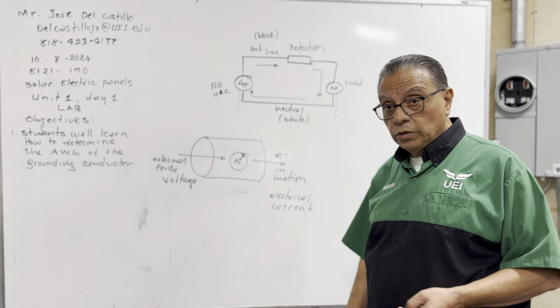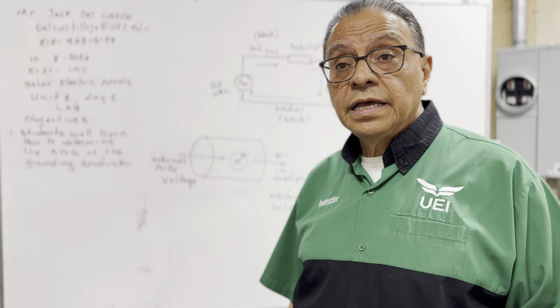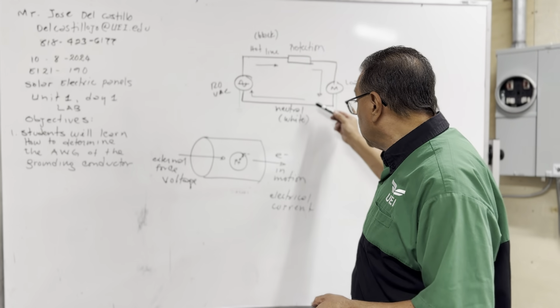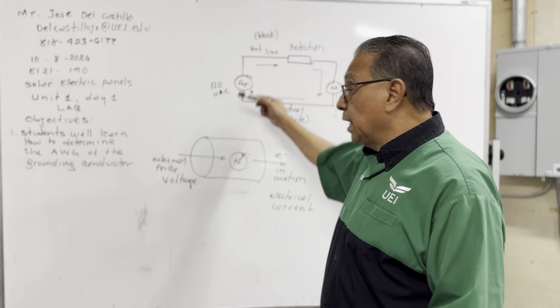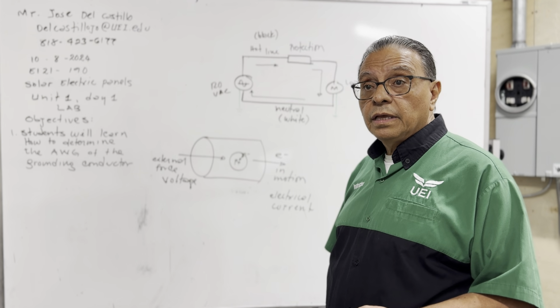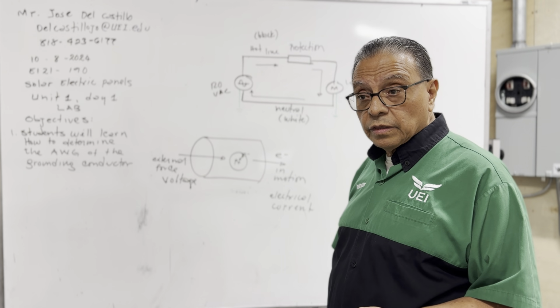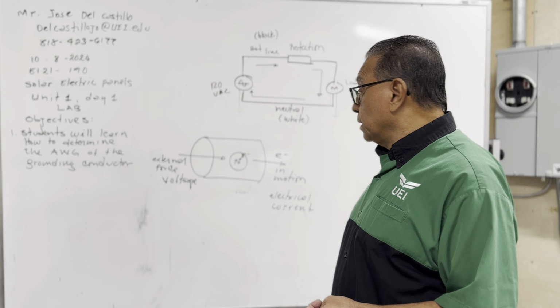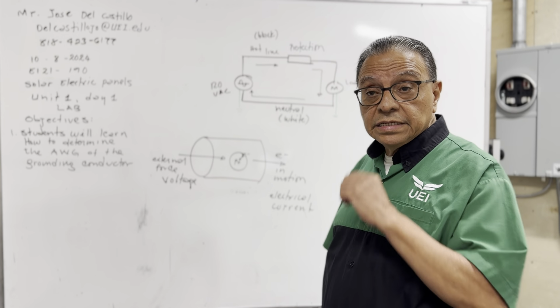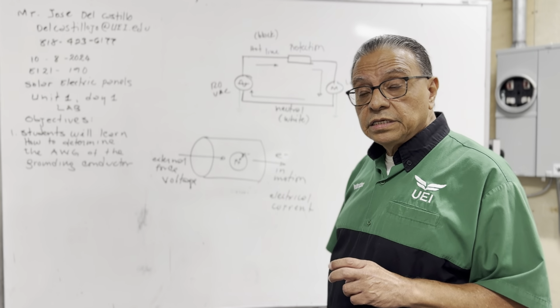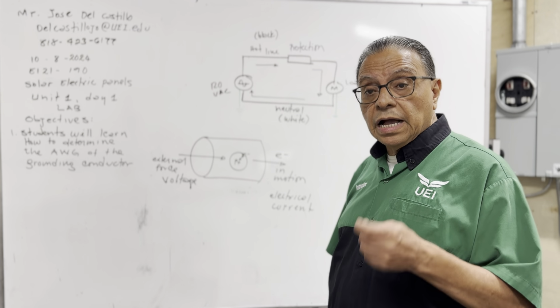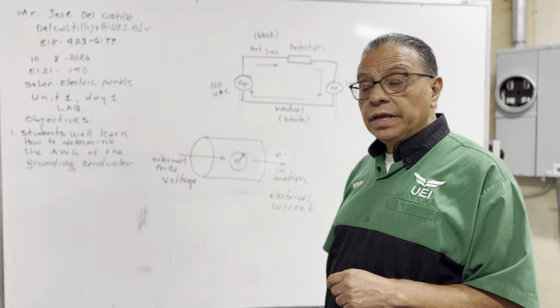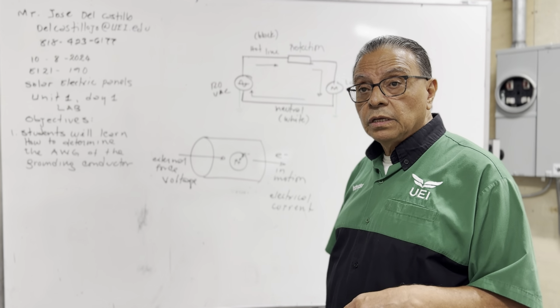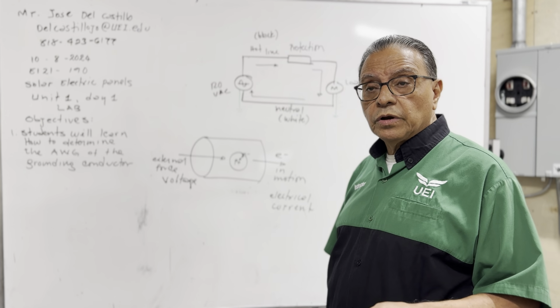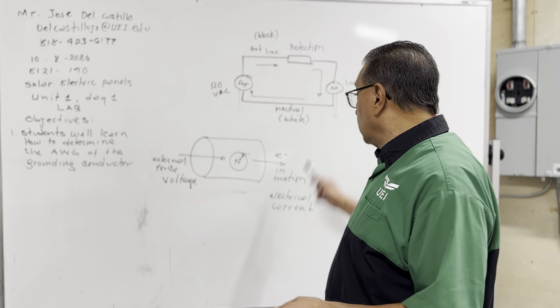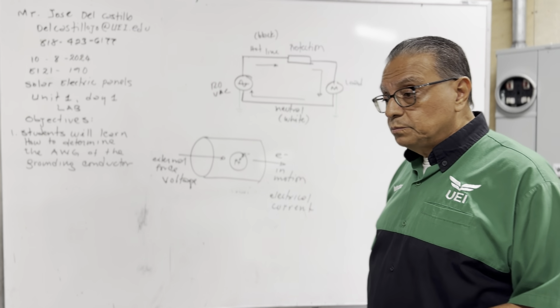That is the reason we have to have a device that will detect imbalance between the neutral and the ground and trip the device, the circuit breaker, okay? The circuit breaker, ground protection. And that is the reason why the NEC requires that we have GFCI or AFCI on the outlets, or a combination circuit breaker that includes both protections, ground fault circuit interrupter or arc fault circuit interrupter, when we have this kind of problem.